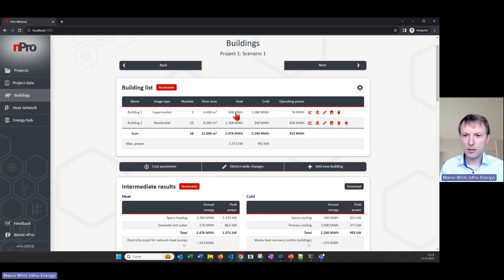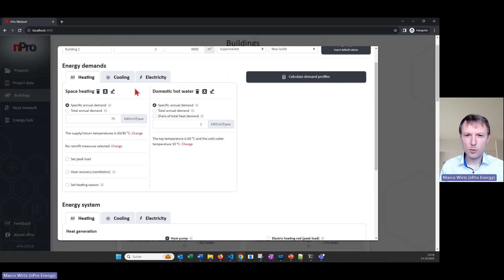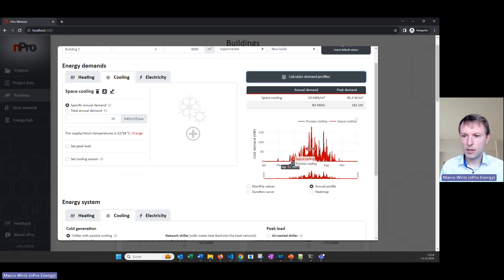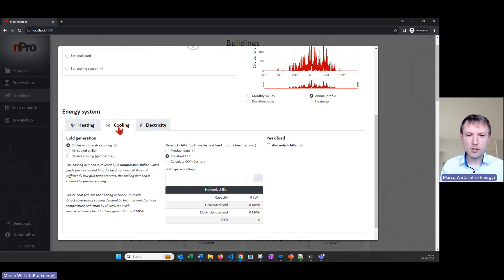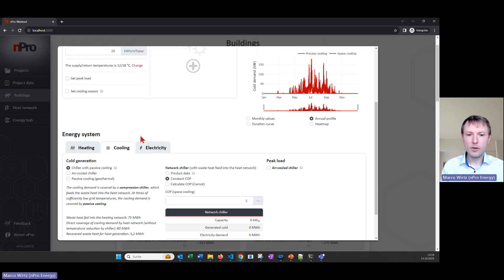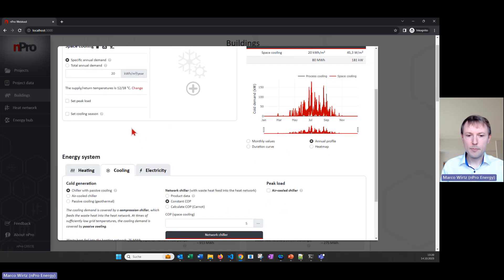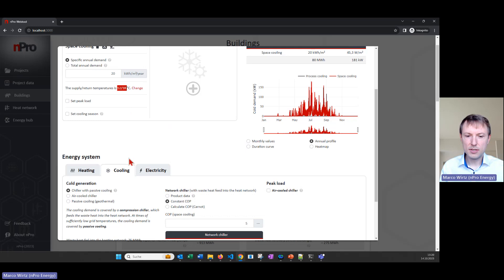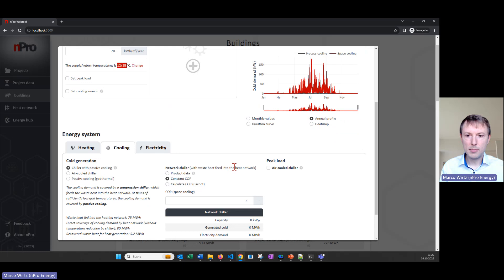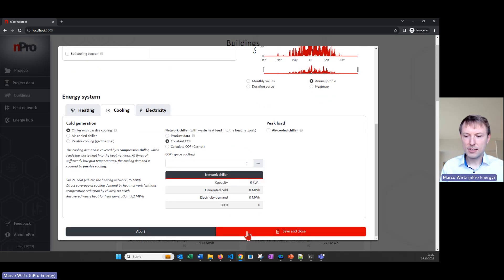For the supermarket I'll go into the settings and deactivate process cooling, since it generates a very large cooling demand. I'll explain how cooling works: if the building has a cooling demand, we can choose the chiller with passive cooling for the fifth generation heat network. This means that if the cold pipe of the network is below 12°C plus a delta-T, passive cooling will be used to cover the demand — the cooling demand here has supply and return temperatures of 12 and 18°C. I'll click 'Save and Close'.